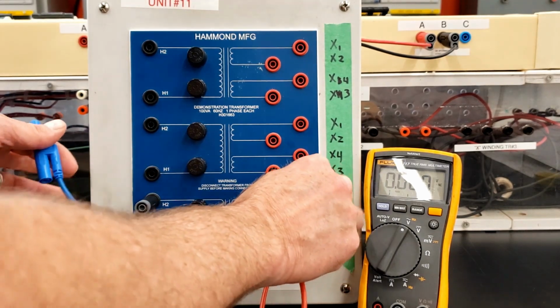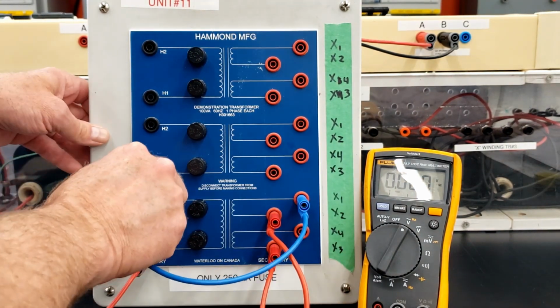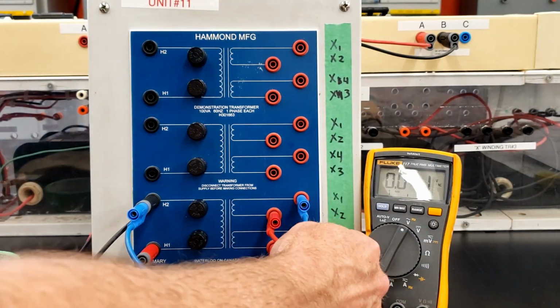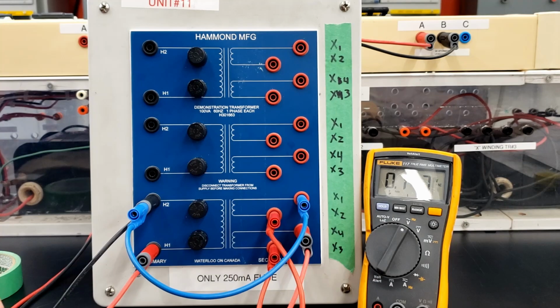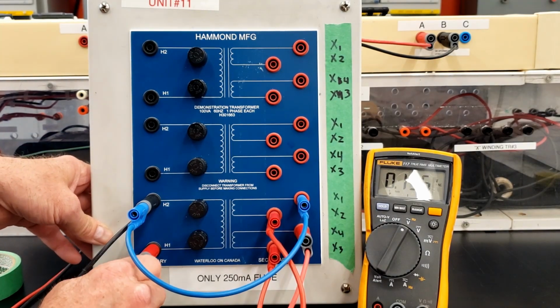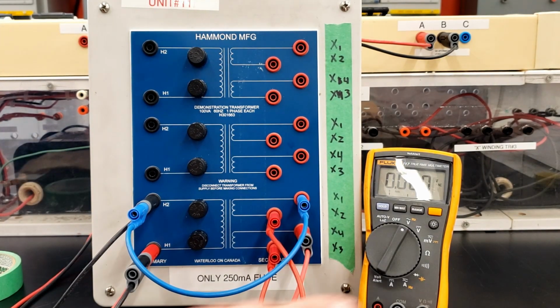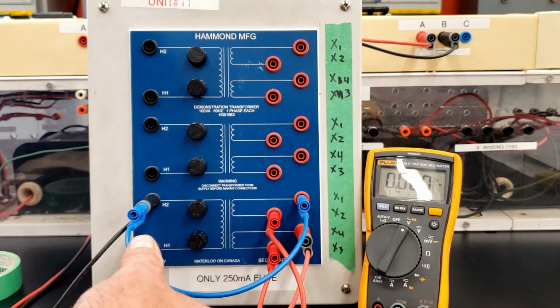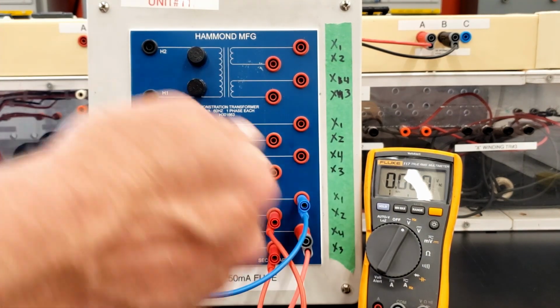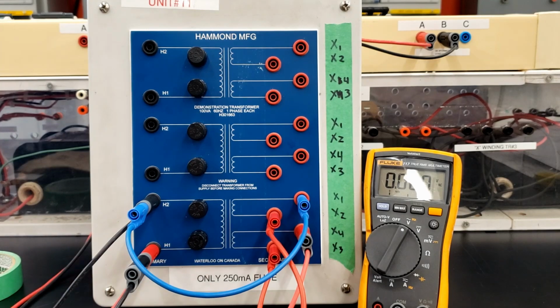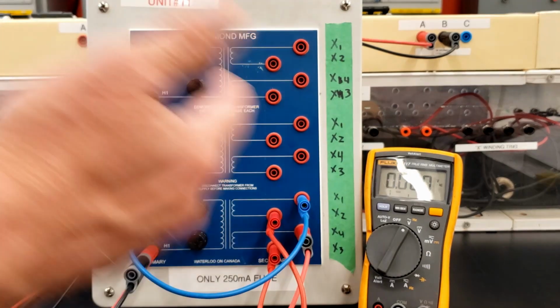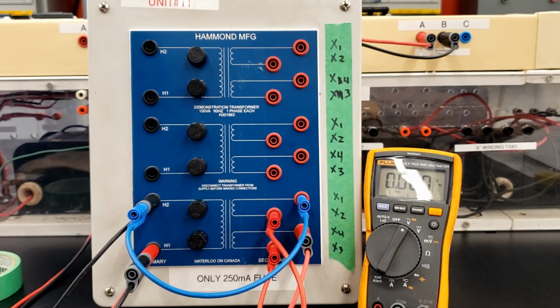Okay, so what I think is X1 to H2. Okay, now I'm going to connect my meter to the two open connections here. And you can also see I don't have power, but if I was asleep at the wheel here and did have power to the circuit, we're using shrouded leads, and so there's no point where I can actually touch anything metal, right? There's nothing grounded around me. So if I was asleep at the wheel and doing this live, I'm supposed to be doing it live, but we should be safe here, right?